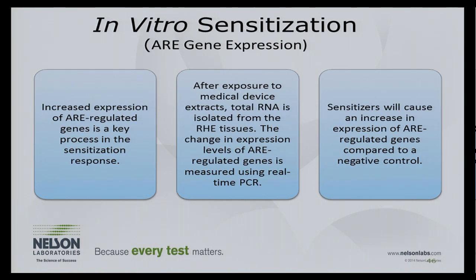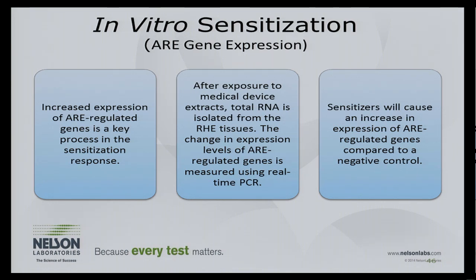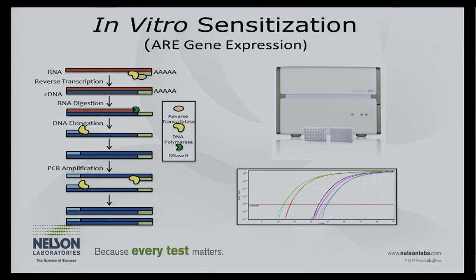The second in vitro sensitization assay uses ARE (antioxidant response element) genes, which are expressed in the presence of a sensitizer. We expose medical device extracts to the same RhE tissues used in irritation testing. Then we break up those tissues, isolate the RNA, and use PCR to measure expression of ARE genes. If those genes are expressed, it indicates a sensitizer is present. We compare expression levels against a negative control to determine sensitization potential.